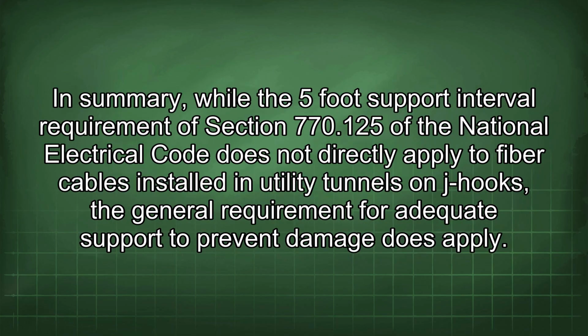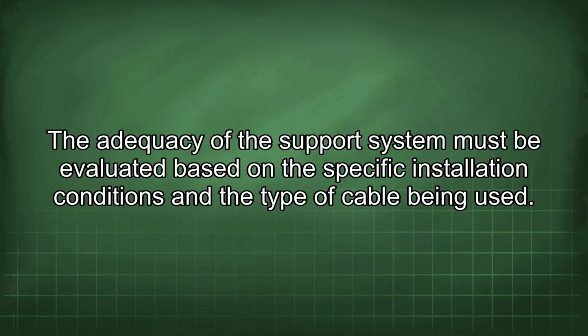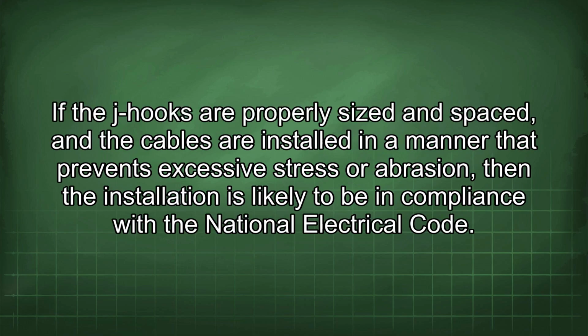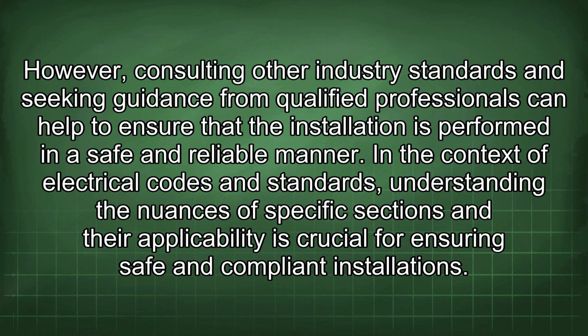In summary, while the 5-foot support interval requirement of Section 770.125 of the National Electrical Code does not directly apply to fiber cables installed in utility tunnels on J-hooks, the general requirement for adequate support to prevent damage does apply. The adequacy of the support system must be evaluated based on the specific installation conditions and the type of cable being used. If the J-hooks are properly sized and spaced, and the cables are installed in a manner that prevents excessive stress or abrasion, then the installation is likely to be in compliance with the National Electrical Code. However, consulting other industry standards and seeking guidance from qualified professionals can help to ensure that the installation is performed in a safe and reliable manner.